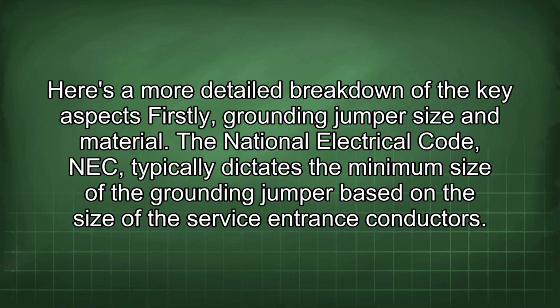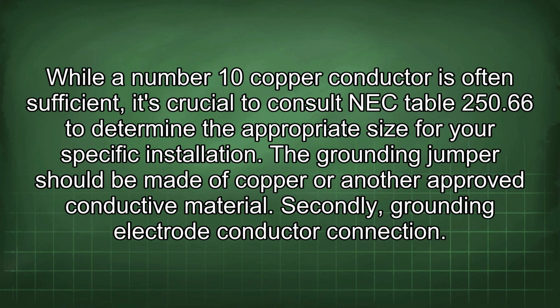Firstly, grounding jumper size and material. The National Electrical Code, NEC, typically dictates the minimum size of the grounding jumper based on the size of the service entrance conductors. While a number 10 copper conductor is often sufficient, it's crucial to consult NEC Table 250.66 to determine the appropriate size for your specific installation. The grounding jumper should be made of copper or another approved conductive material.